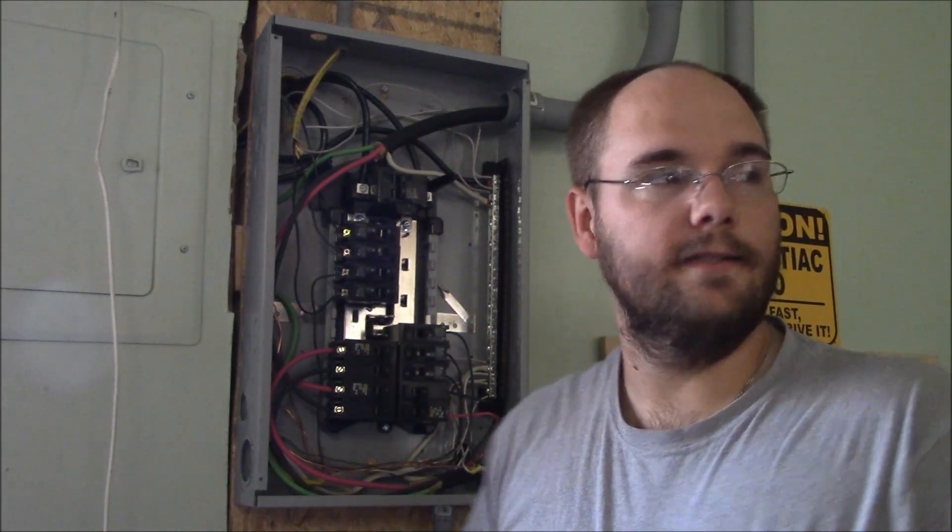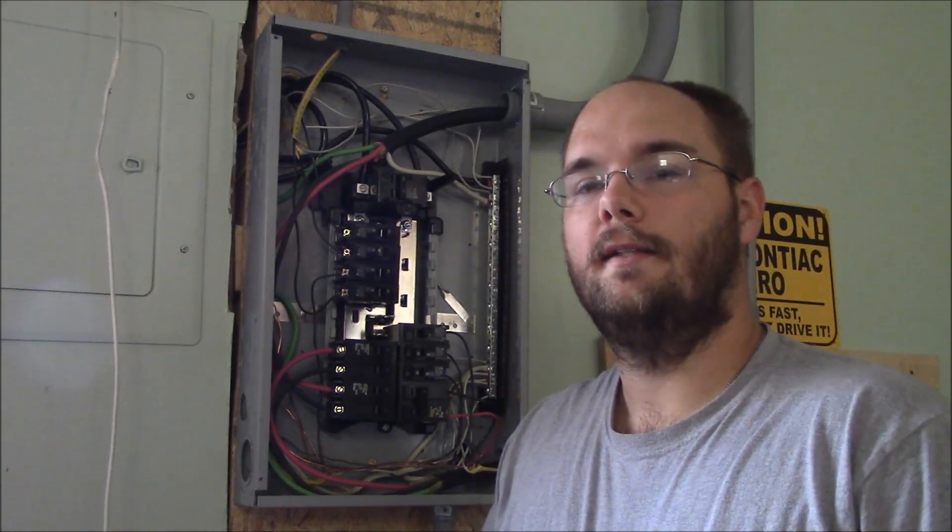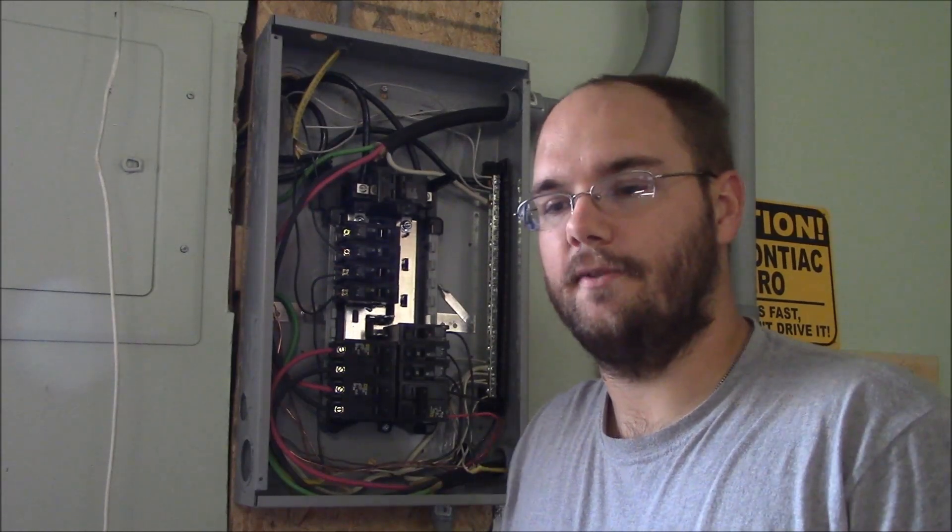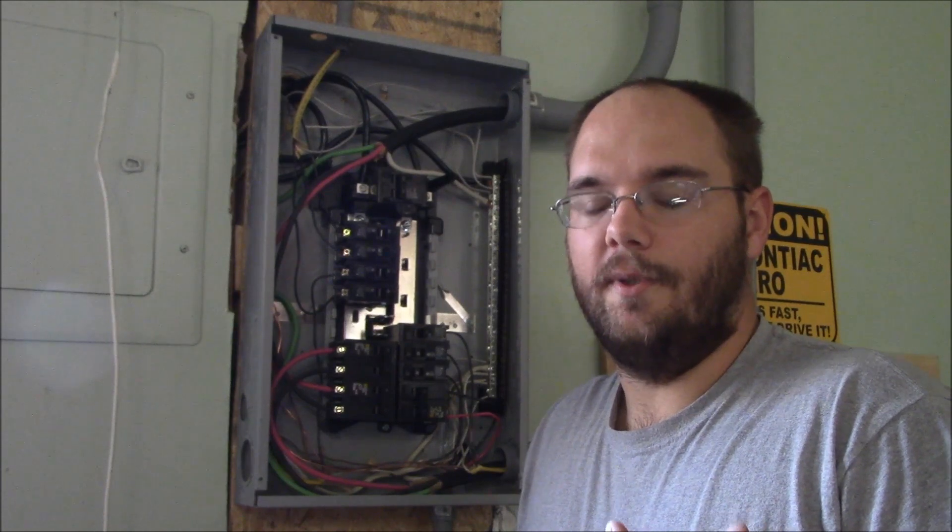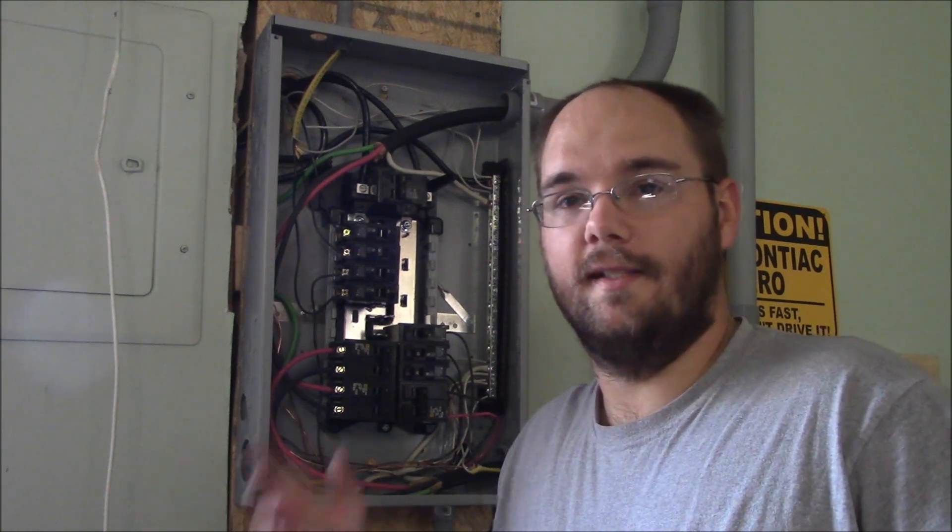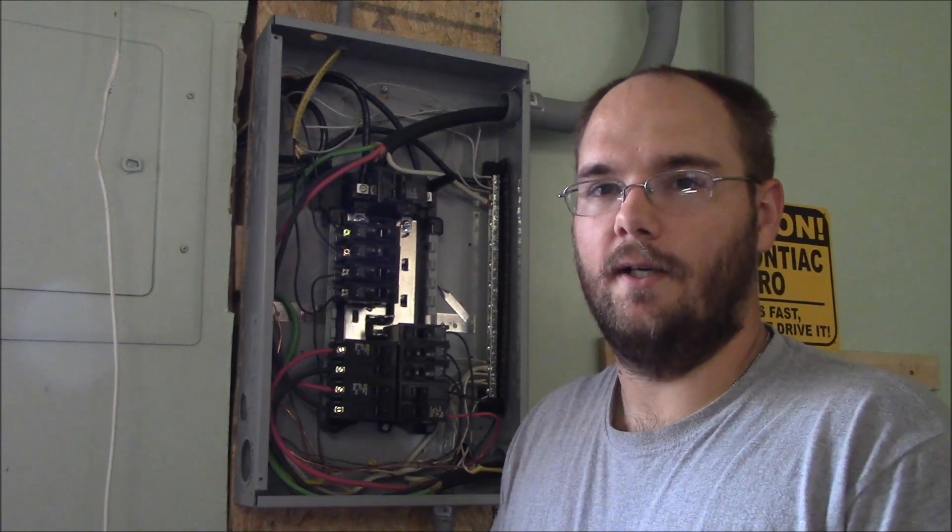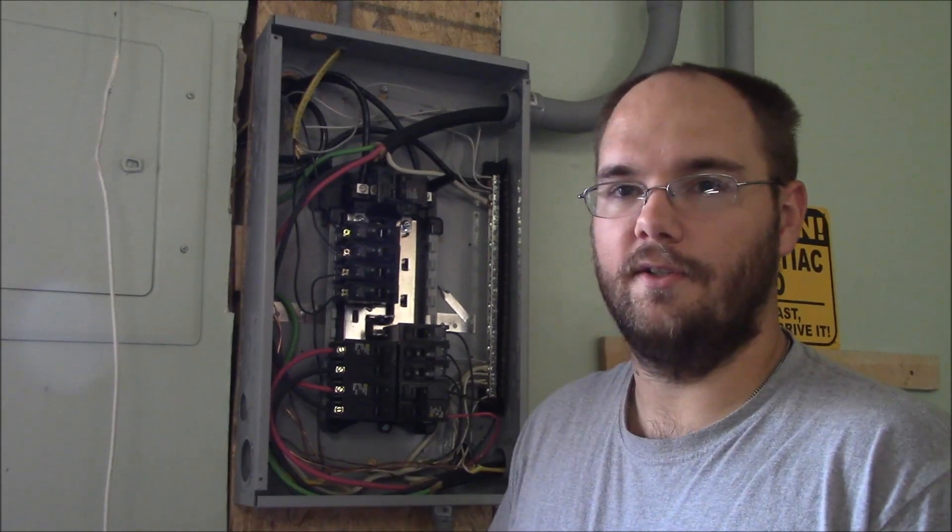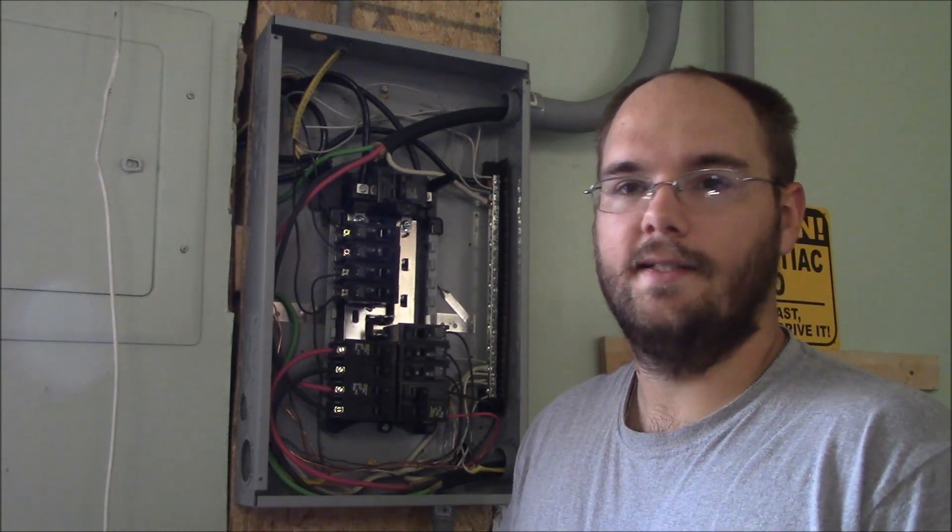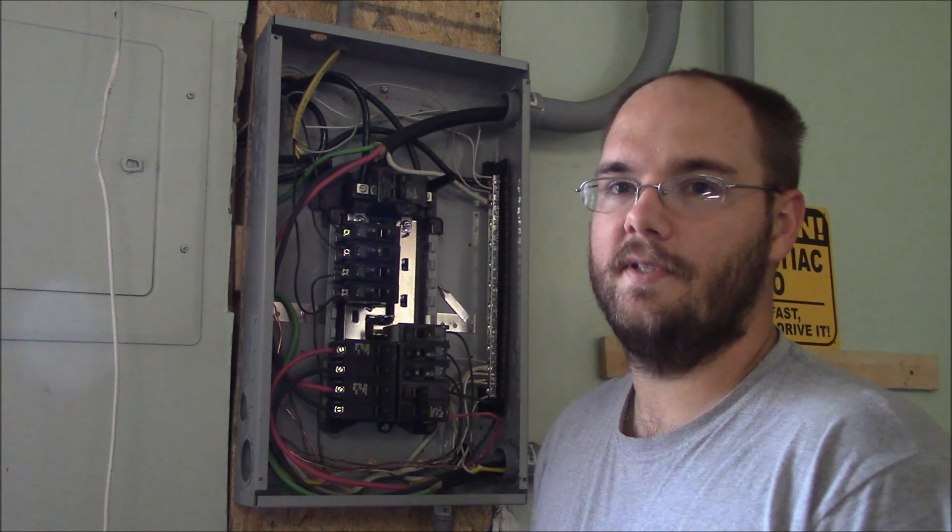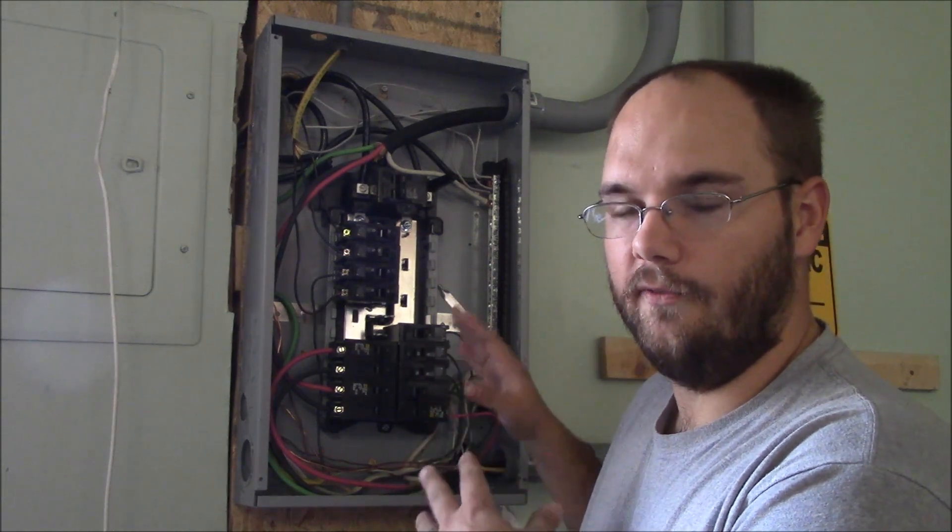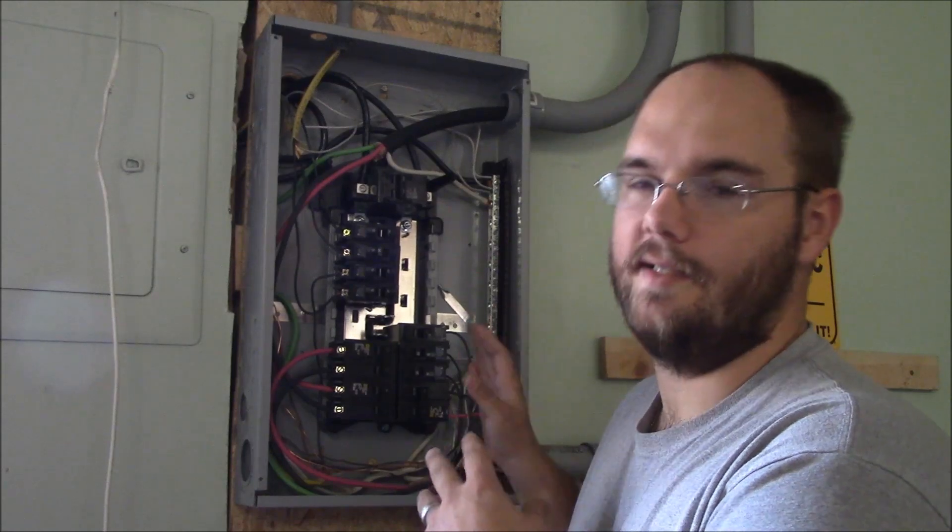So to test this, I mean, it's going to be connected to some switches down the way into the lights, and I don't really have any of that connected in yet, so I can't really test it right now. But to test it, it's going to be a matter of flipping the light switch—do the lights turn on? Or flip the light switch—does it instantly trip or something like that? So I hope that this was educational to you. This is a 20 amp—you can use the same process for 15 amps, 30 amps, pretty much any 110 or 120 volt breaker. That's your process.